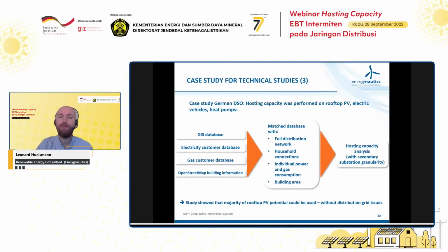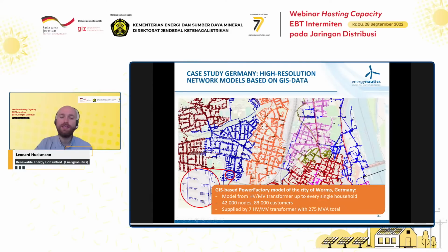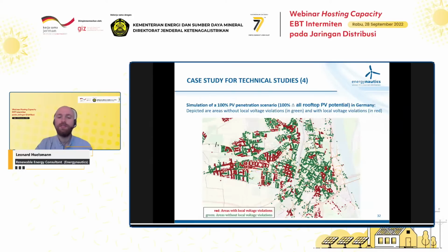Here's also an example from Germany, where we did a number of studies with a German utility, combining lots of data sources to produce very detailed distribution network models. This is the entire distribution network of a city in Germany with 83,000 customers, modeled in very high detail down to each and every house connection. This is an advanced option that may be possible at some point, but it requires a lot of data and analysis. On this network we ran simulations of how a certain PV penetration scenario would impact voltage quality, showing where the limits of maximum PV penetration lie.